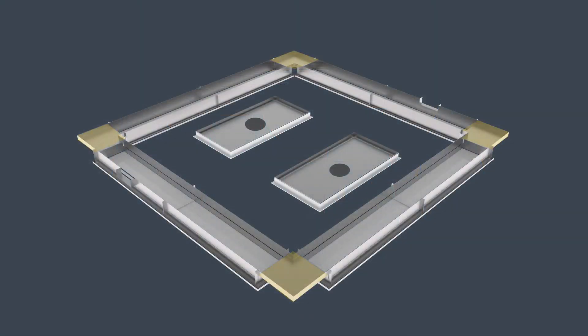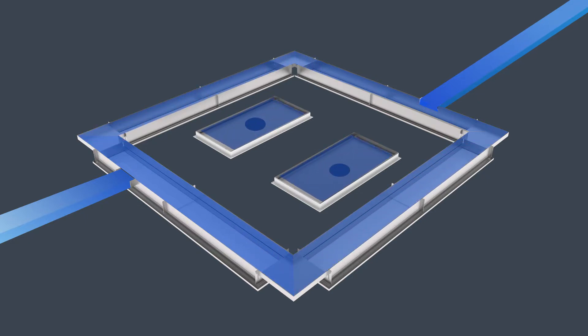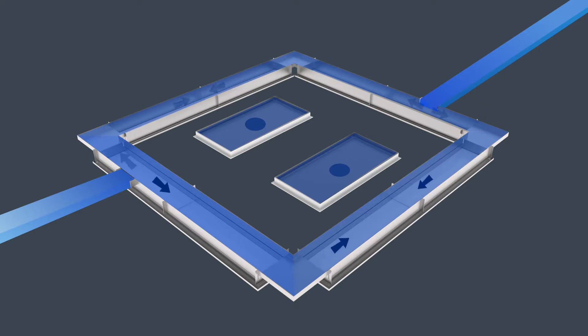The Paraflow System incorporates elbows to connect the multiple sections of the perimeter slot diffusers that form a continuous loop of the entire curtain. This loop only requires two total supply connections regardless of the size, and creates a self-balancing system that will never require rebalancing, reducing labor and materials dramatically.